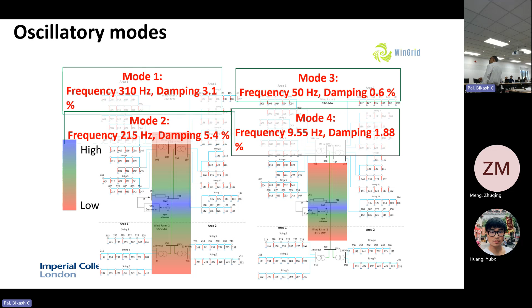Then we move to a different operating condition, since sometimes some turbines are up and running while others are down for maintenance. For example, if only 3 to 5 turbines from area 2 are running and all other turbines are down for maintenance, the last turbine in the string feeding 5 megawatts has to travel the whole distance. That's the most onerous situation.